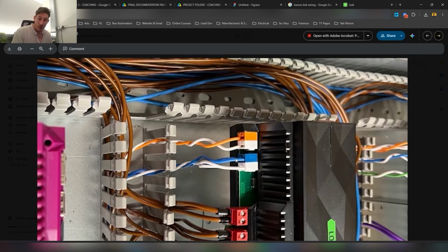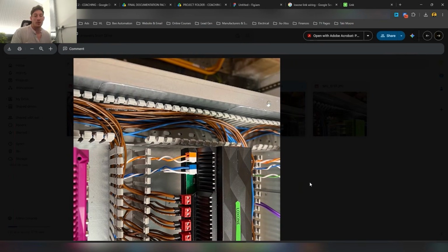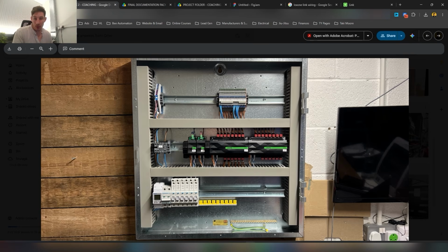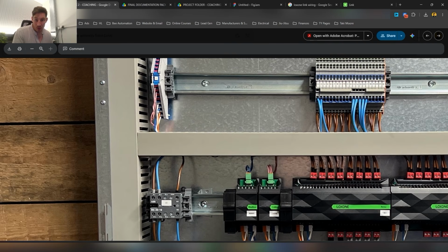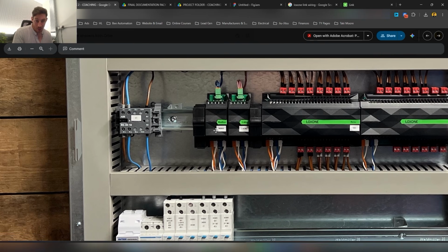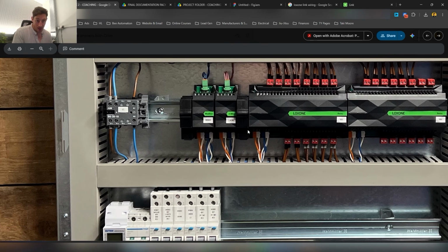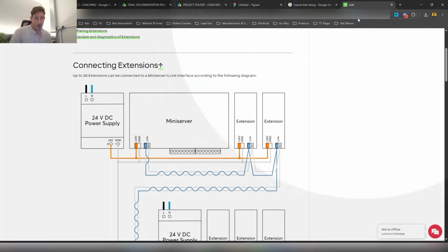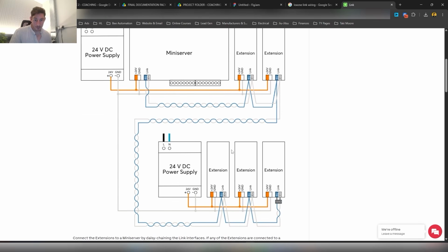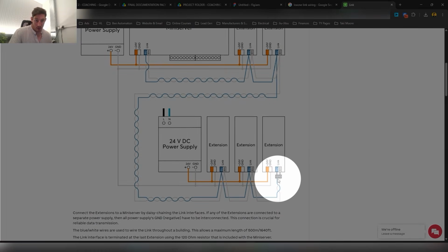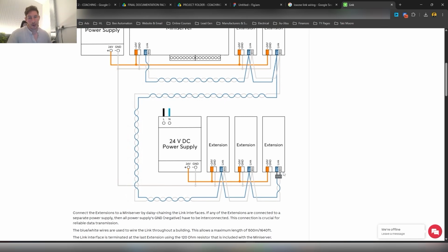But then these tails go off to the terminal blocks because we're then continuing that link connection over to Lox 2. So as you can see here, that Loxone link is coming in here and then being distributed into these devices as well - the Modbus extension, the one-wire extension, the relay module - and here you can see that is the final point on the line, where it's recommended that you then have a 120 ohm resistor on the final extension.